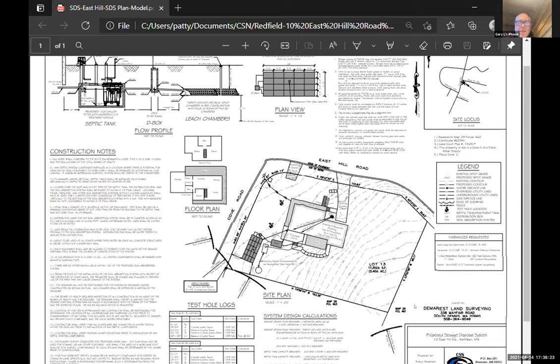I have the same comment for this plan as I had for Jason's plans, in that I believe at least one cleanout should show on the building sewer to the septic tank. I believe there is a building sewer inside the house, which is standard. You want something in between that and the septic tank? Yeah, because technically Title V says at all angle points, but you only really need to put one. So I would put one maybe at the first angle point. Okay. And that's my only comment. Thank you, Gary. And Nick, do you have anything to say? No, I'm all set. I was just wondering about the wells, but they were pointed out. I'm all set also.